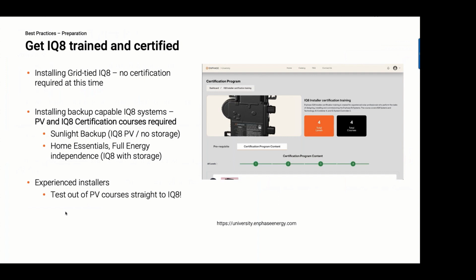If you are installing IQ8, then there are some training requirements. If you're installing grid-tied IQ8, no backup system, you don't have any certification requirements. You can continue to install IQ8s like IQ7s, and there's no additional training that Enphase requires. However, if you're starting to install IQ8 where it's in a backup configuration, that's sunlight backup, or one of the ones with batteries, then you're going to have to get certified with IQ8. Even if you're storage certified today, if you're going to install IQ8, you still have to go back and get the IQ8 certification also. And then you'll need to be PV certified.